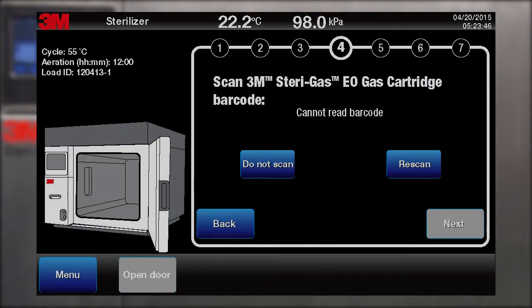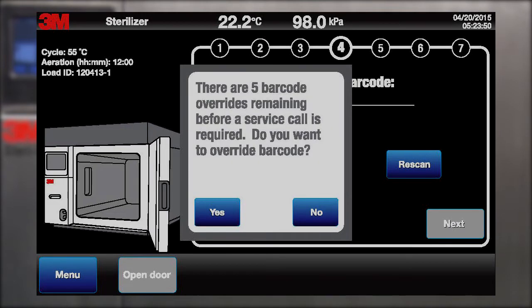If the cartridge barcode is not valid, the screen will display a "Cannot read barcode" message. At this point, the touchscreen will allow you to select either Do Not Scan or Rescan the current cartridge. If you select Do Not Scan, only 5 scanning overrides will be allowed. After 5 instances, you will need to call Service to clear the scanning overrides.